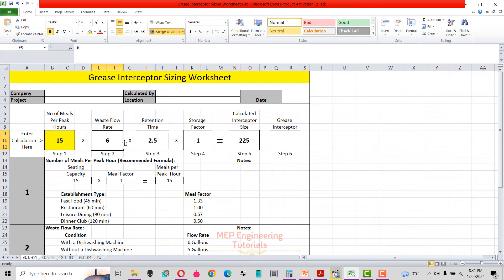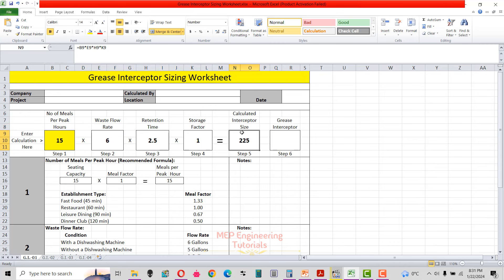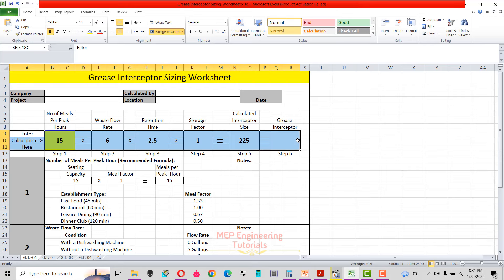Then we have to get the waste flow rate and the retention time, then the storage factor. Once we have all that information from steps one through four, we multiply all those to get the interceptor size. Once we have the interceptor size, we select the interceptor from the approved supplier's catalog.